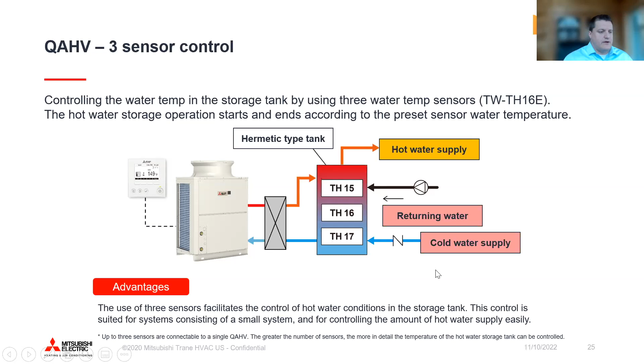Where the 6 sensor control comes into play is when you have more advanced control scenarios, particularly demand response. So when you've got direct utility engagement and you're running the heat pumps, the same concept applies. It's just 3 more sensors. So you may allow it to ride out or deplete the tanks more and not turn on at a different sensor, or you might turn it on at a different sensor for various reasons.